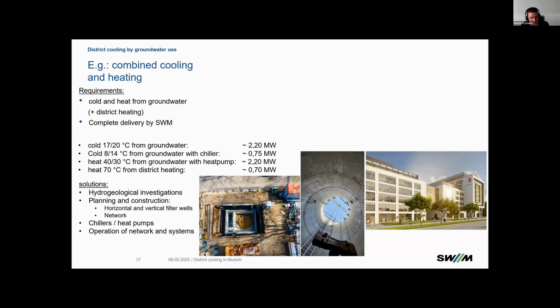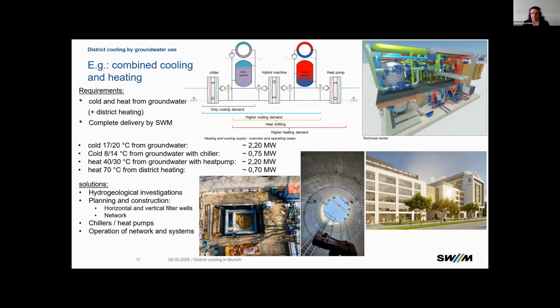In addition to transporting the groundwater to the buildings, we installed chillers and heat pumps for the cooling and heating demands. And in addition to that, district heating, because he needed around 0.7 megawatt at 70 degrees, which is better with district heating. And since we installed that system, we are doing the operation of the network and the systems. As you can see here, on the right side, it's a technical center with the heat exchangers, the heat pumps, the chillers, and so on. And in the middle, you can see that we're not only delivering the groundwater and the temperature with chillers and heat pumps, but we also use some heat and cool shifting inside the system.